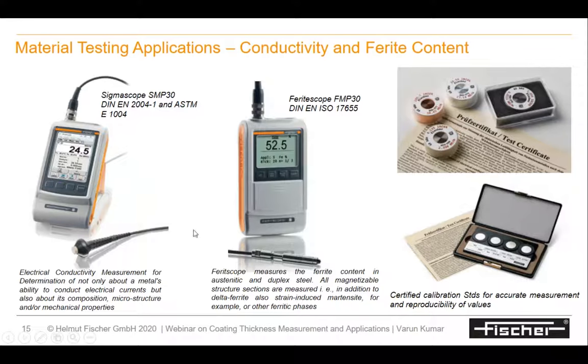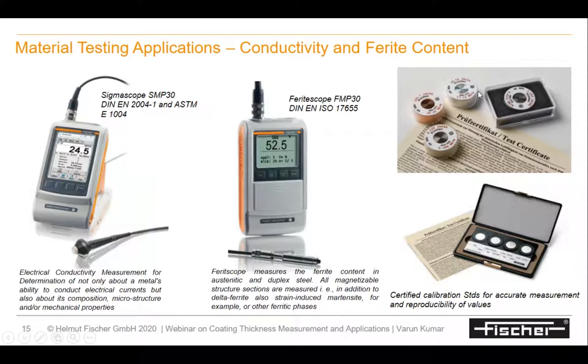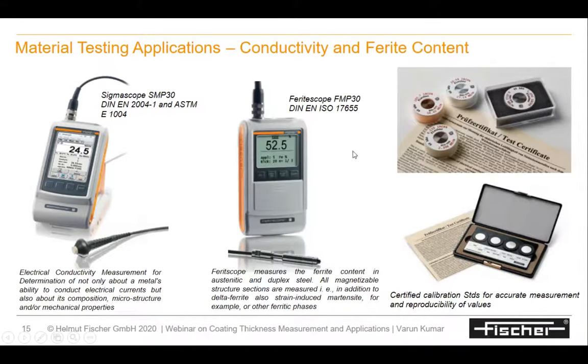Both the Sigma Scope and Feritscope are successful largely because of the calibration standards Fischer provides. The Sigma Scope comes with a 14-set standard meeting Boeing requirements. The ferrite calibration set covers the entire measurement range. Fischer's own calibration laboratory in Germany prepares and calibrates these standards in-house. Customers can also send their standards to be calibrated at this facility.